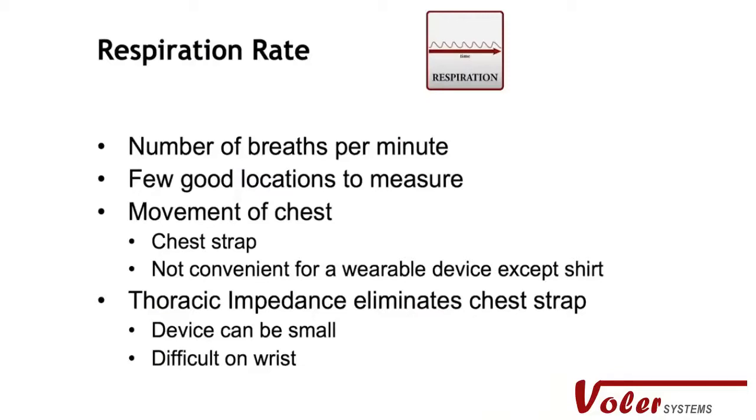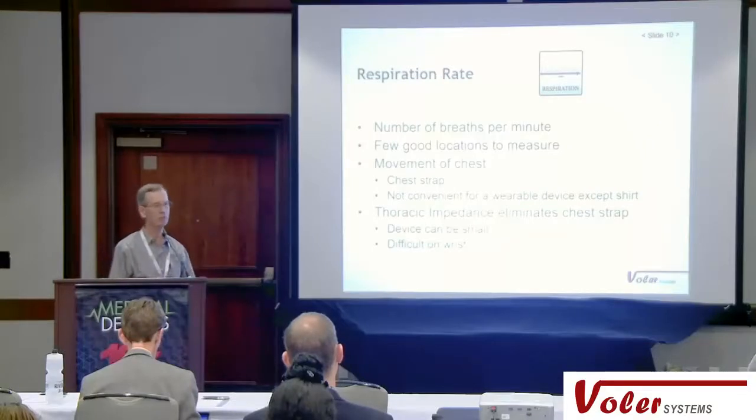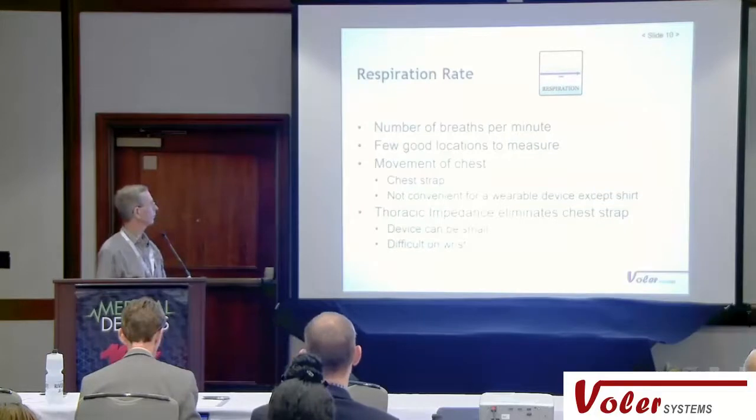Respiration is another very important parameter. The standard is to put on a chest strap, which is easy to measure but inconvenient for a wearable. Another way is thoracic impedance — you measure the impedance of the chest, which changes as you breathe in and out. But this needs to be on the chest. People would like to put it on the wrist, but I haven't seen it actually work, because the wrist has a large impedance — your arm — between it and the chest, which makes that signal much smaller and very difficult to detect.